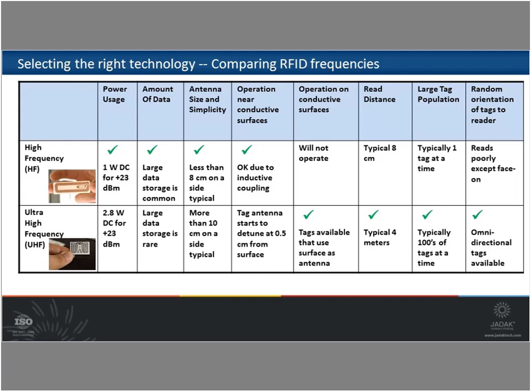A customer who still manufactures laser scalpel control units needed to be able to identify the type of laser scalpel in order to auto-configure the control unit and have the correct settings for the specific scalpel being used. Originally, barcodes on the scalpel connector were used to transfer this information, and a reader on the control unit would identify by that barcode which scalpel it was. But barcodes tend to wear off with handling—if they get dirty at all, they don't read as well.